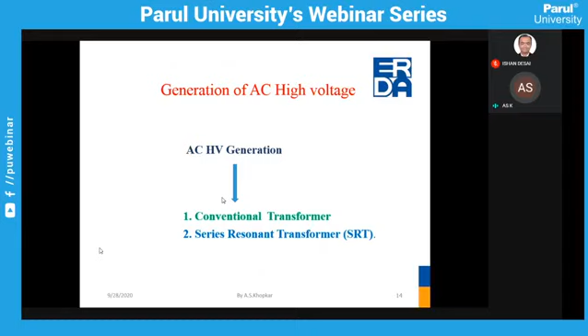See, this is how it is different from the normal transformer, power transformer or distribution transformer. First of all, it has a very low VA rating. The distribution transformer is rated 25 kVA, 100 kVA, 500 kVA, 630 kVA, or the power transformer ratings are in terms of MVA. So here the VA rating is very low, meaning current is very low. A few ampere or milliampere, meaning 0.1 ampere, 1 ampere, 2 ampere. That's all, not more than that.